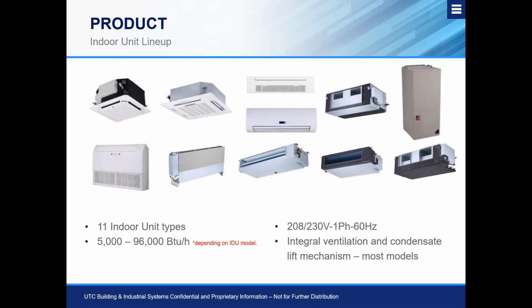So, for example, the compact and 3x3 cassettes, the traditional style cassettes, have an outside air knockout, so we can pre-treat outside air and put it directly into that cassette style unit. And both of those have a condensate lift with a different lift rating that we can use to remove that condensate, either to a secondary condensate pump or to a natural drain. The high wall and the one-way cassette do not have outside air intakes, except for a specific range on the one-way cassette short.